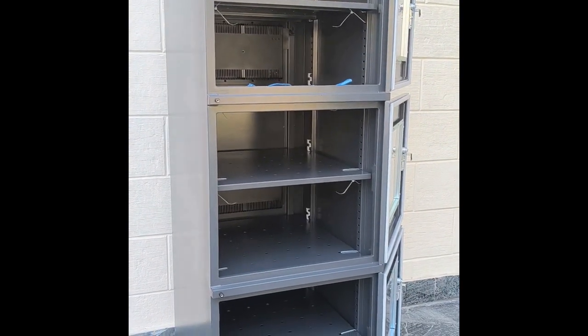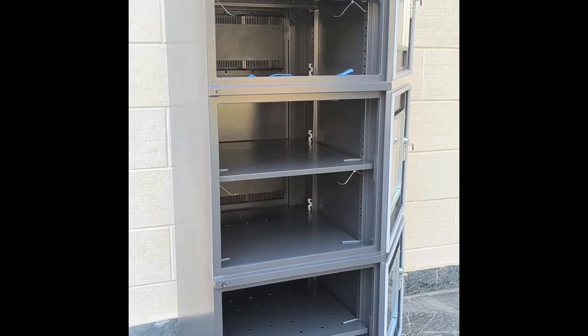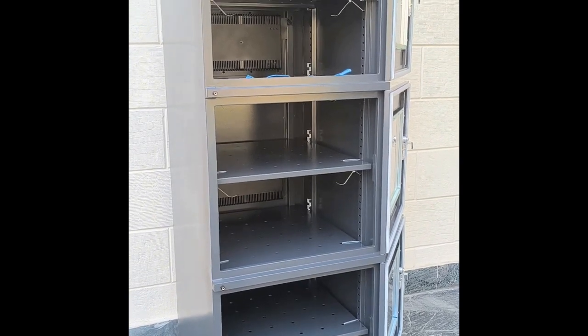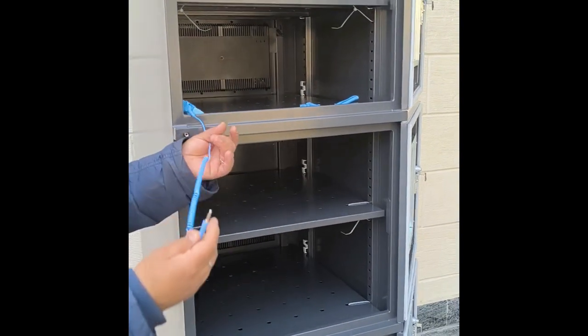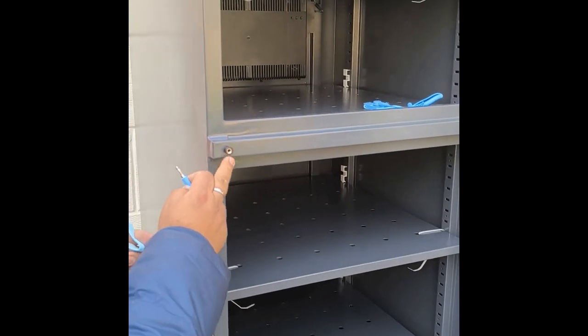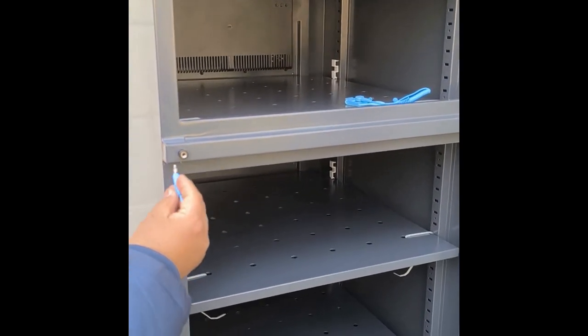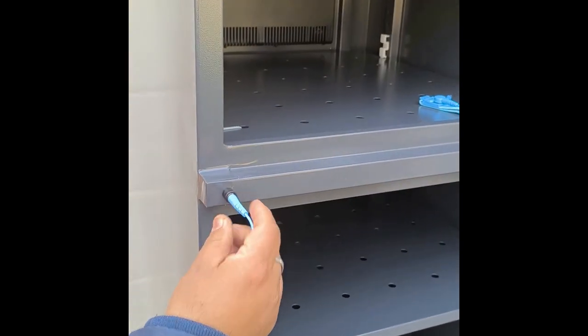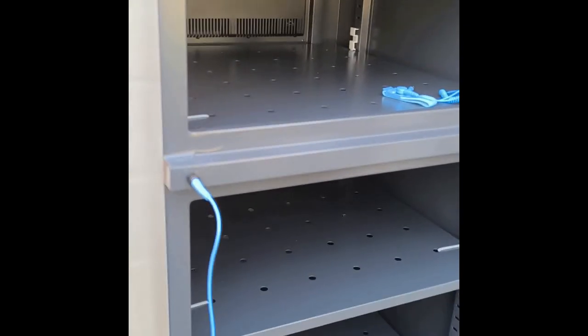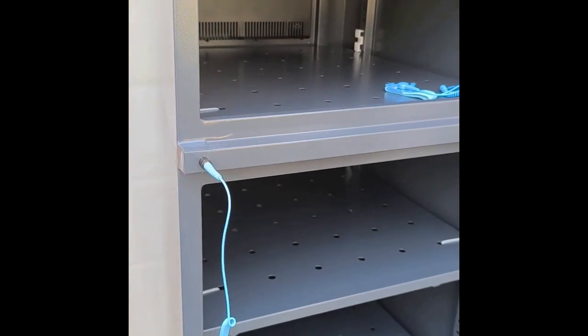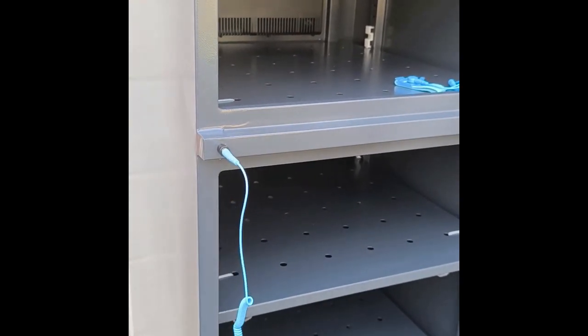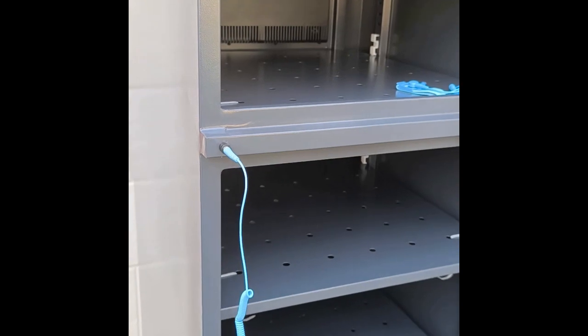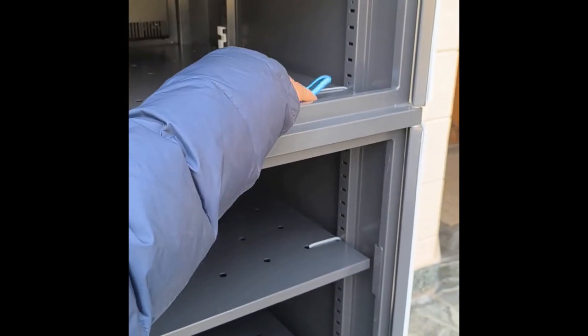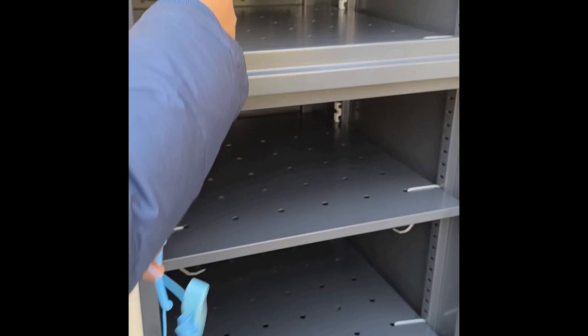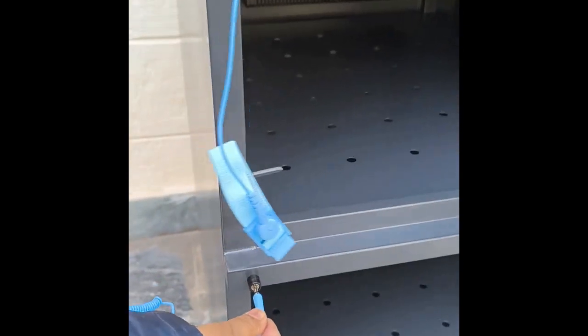Let's see how we can use the wrist strap supplied along with this dry cabinet. There is a banana socket mounted on the dry cabinet, and on the wrist strap side there is a banana plug. We need to insert this banana plug into the banana socket to connect the strap to the dry cabinet. Before opening the door, the user should wear the wrist strap and then open the door to maintain this static sensitive area. There is another strap also, and the same procedure is followed to connect it to the dry cabinet.